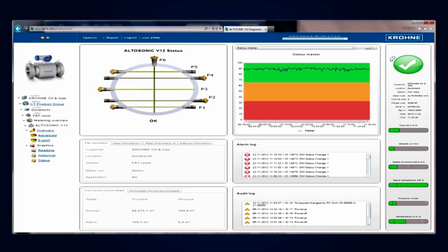First thing you see is a green V, indicating the overall health of the meter. This meter is running fine at this moment in time. You see some basic data, such as the flow rate in the meter, the flow velocity in the meter, the speed of sound of the gas in the meter, in this case atmospheric air, and the signal acceptance of the different acoustic paths. In case pressure and temperature transmitters are connected, you see a live reading here. For this setup that's in our FAT room, we just plugged in a fixed value for pressure and temperature, since we have no transmitters connected.